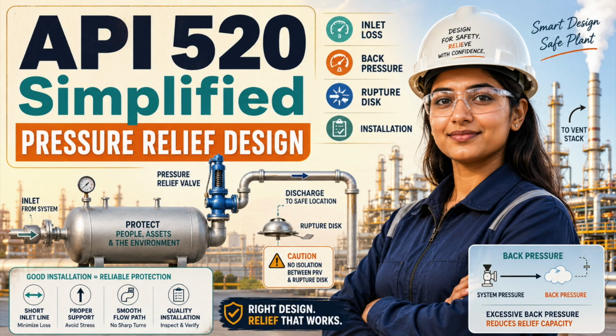You must also understand what a pressure relief device can and cannot do. It protects against overpressure. It does not protect against every failure. It cannot repair lost wall thickness, prevent brittle fracture, overcome blocked discharge piping, compensate for a closed isolation valve, restore material strength during prolonged fire exposure, or correct an incorrect process scenario. It will not save equipment from every structural, thermal, chemical, or mechanical failure. A relief valve is a safeguard, not magic.